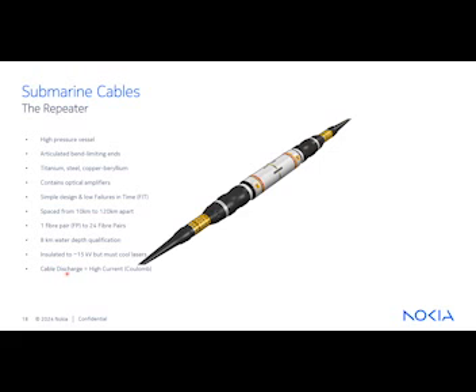Now, this is a big problem — the cable is largely, as you know with coaxial cables, a large coaxial capacitor. So if we put 15,000 volts on this capacitor and it gets cut, that will discharge quite quickly, and you can get upwards of hundreds of amps. These are qualified for 500 amps blasting through them before you have significant problems, but it can be an issue.